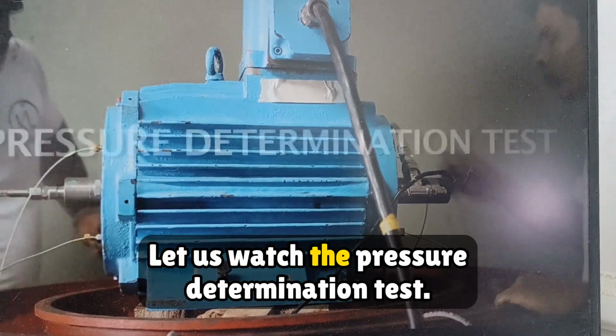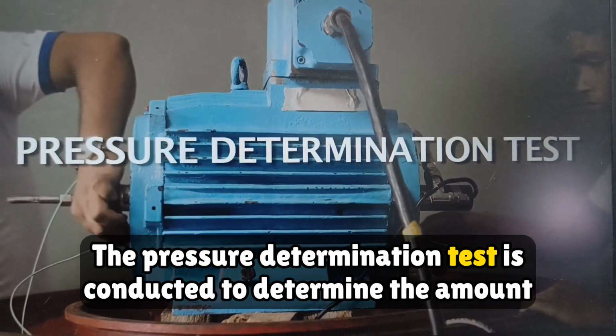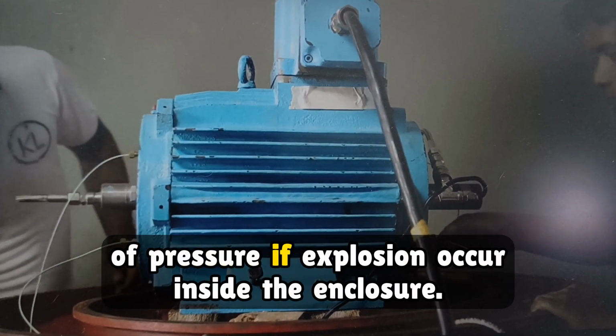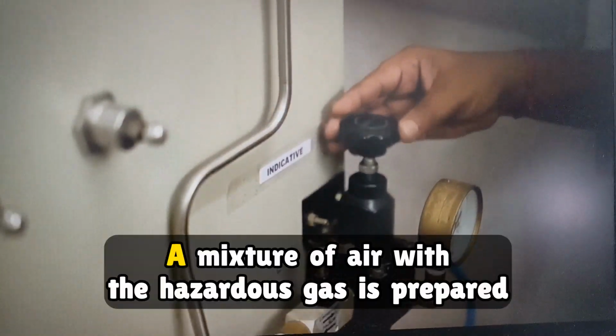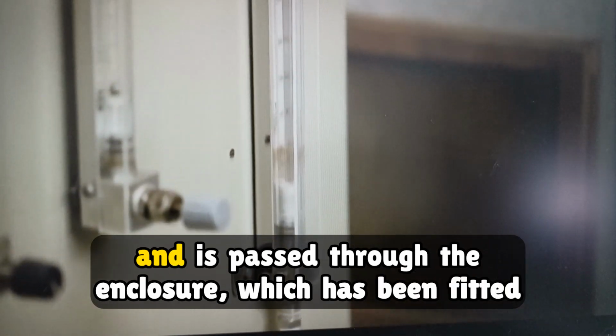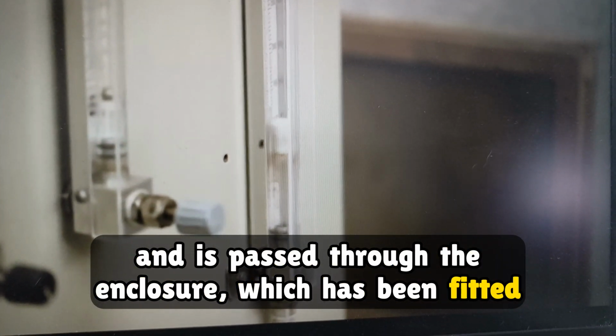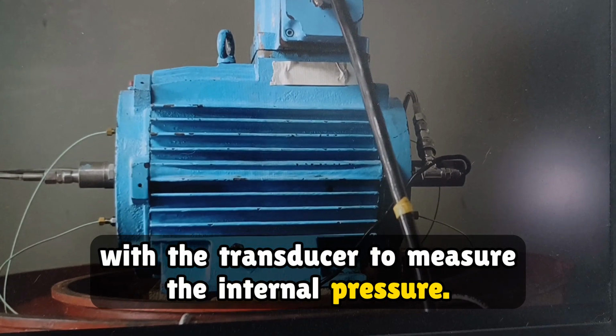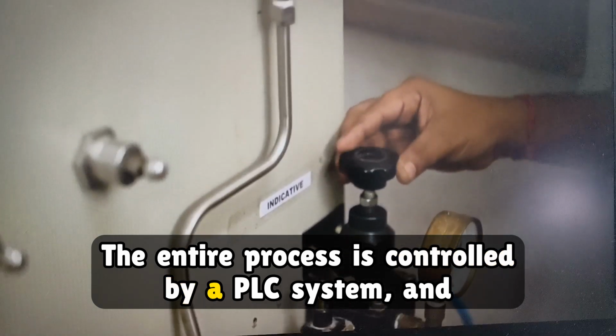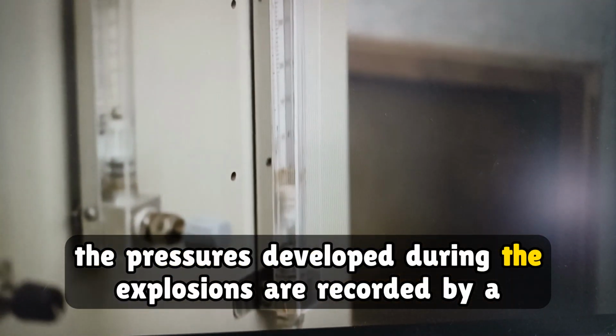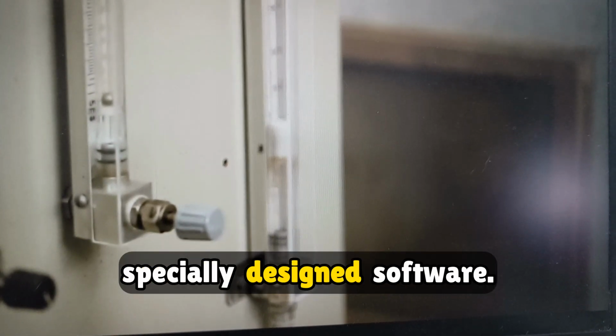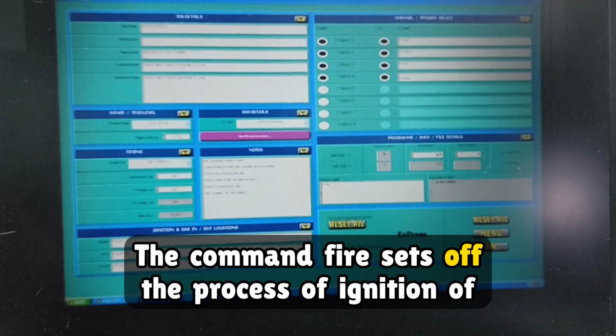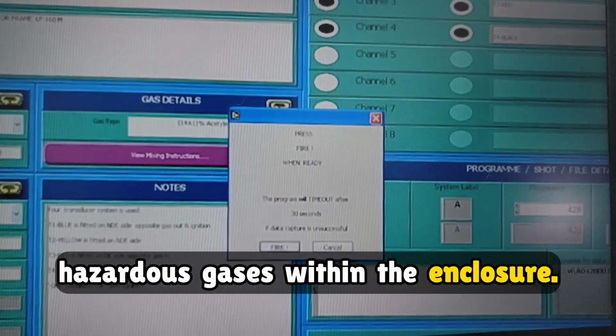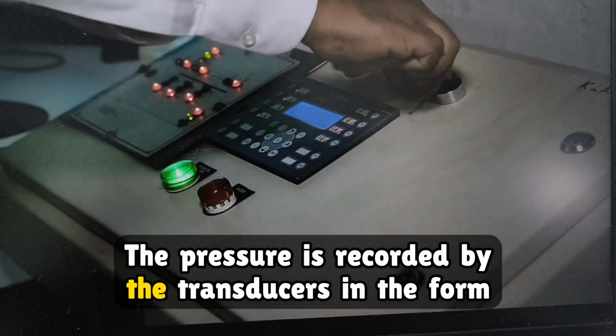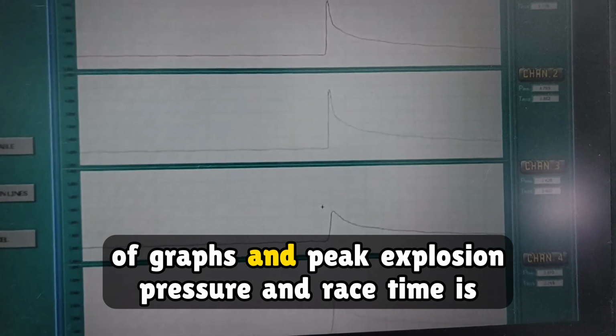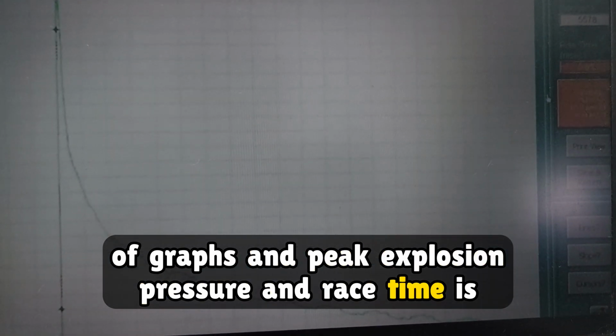Let us watch the pressure determination test. The pressure determination test is conducted to determine the amount of pressure if explosion occurs inside the enclosure. A mixture of air with the hazardous gas is prepared and is passed through the enclosure, which has been fitted with a transducer to measure the internal pressure. The entire process is controlled by a PLC system, and the pressures developed during the explosions are recorded by specially designed software. The command fire sets off the process of ignition of hazardous gases within the enclosure. The pressures recorded by the transducers in the form of graphs, and peak explosion pressure and rise time are noted down for further analysis.